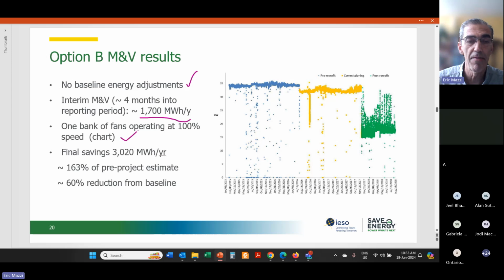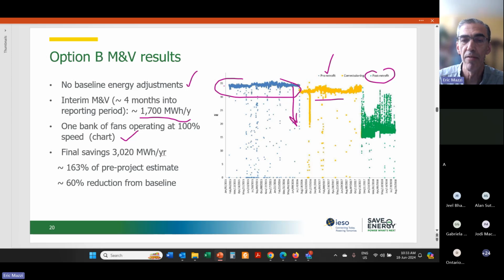It was discovered that one bank of fans was still operating at 100% of full speed. In this chart, this just shows one fan or one bank of fans. I don't think this was the one that had not been programmed correctly, but the blue was the pre-retrofit or baseline. There was a commissioning period here, and then the post-retrofit is in green. You can see the power consumption came down quite a bit, from roughly 35 kilowatts to roughly 17 or 18 kilowatts, something like that.